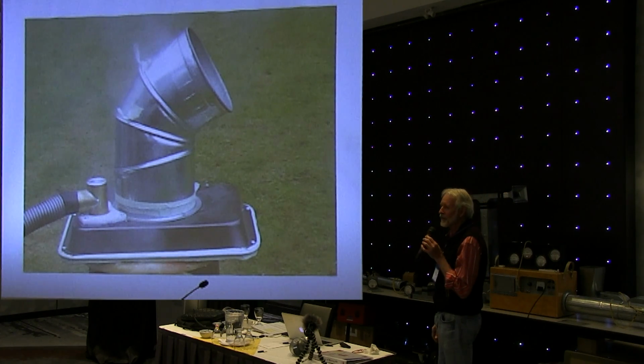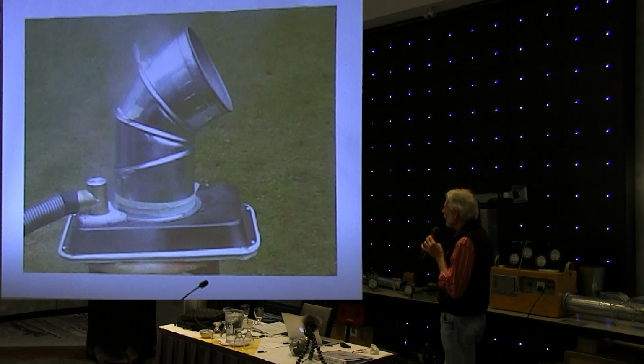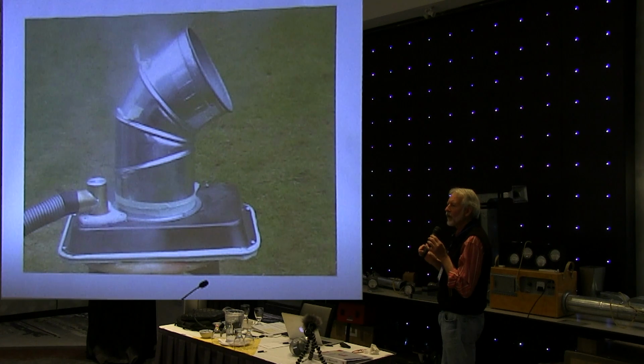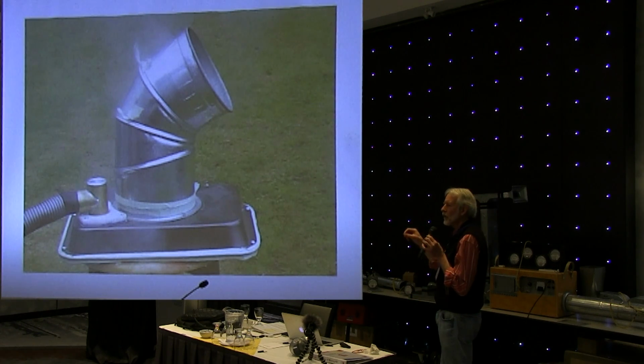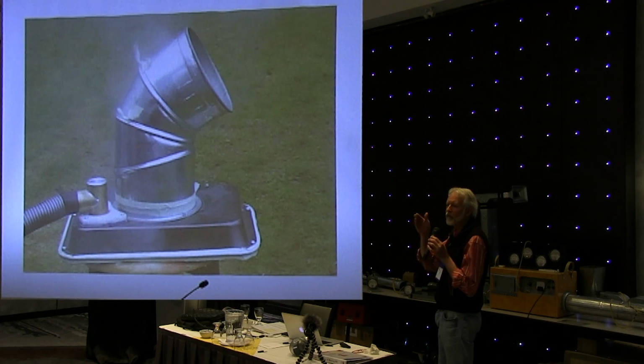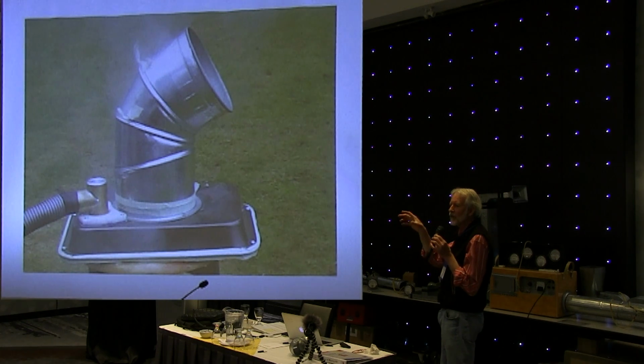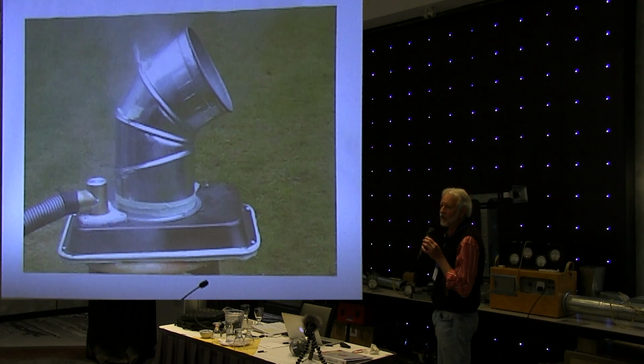But the bottom line is, this is quite illustrative to the trade, and they're absolutely blown away when they see it for the first time, because in Canada, we've never, ever questioned adequacy of duct in a system before. And we've been getting away with it because we've had cheap electricity, we've had forgiving appliances that run at very high temperature rise, so they're becoming forgiving simply because they tolerate this restriction because they can take the high temperature.